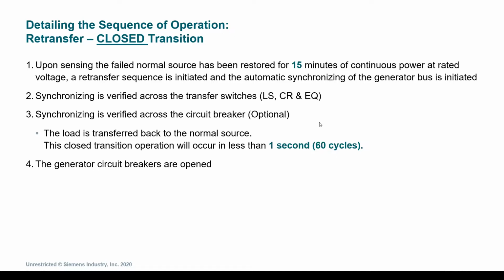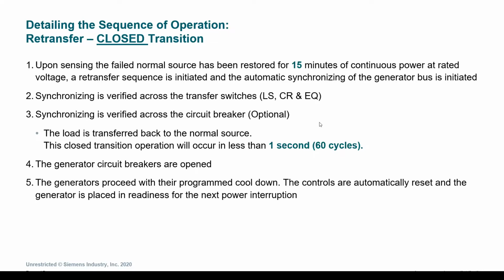At this time, all of the transfer switches are back in their normal source and the generator circuit breakers are open. From here, the generators proceed into their program and the controls are automatically reset and the generators are placed in readiness for the next power interruption. At this time, the system is returned to normal operation where the generator circuit breakers are open, the branch circuit breakers are closed, and again, the generators are sitting in readiness.